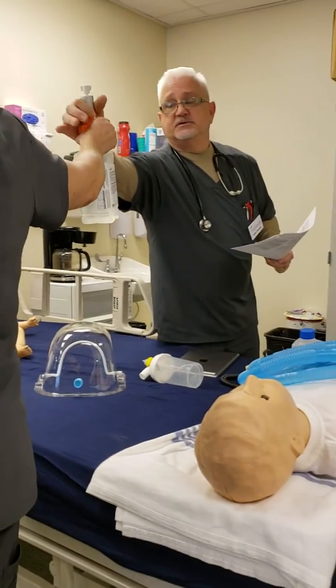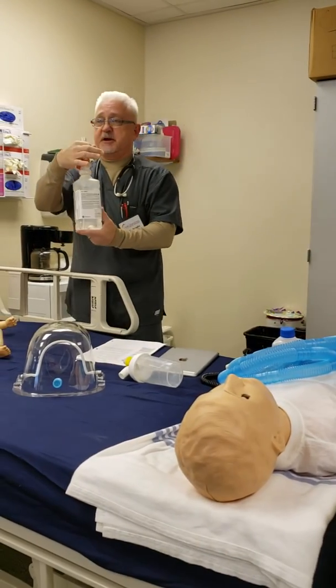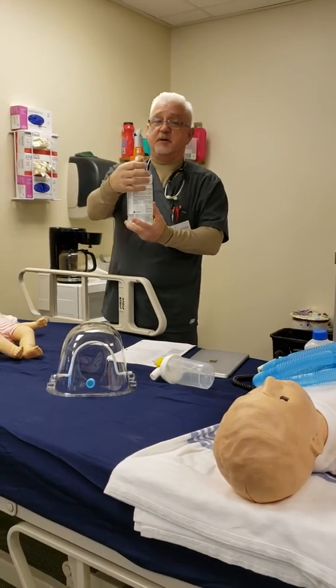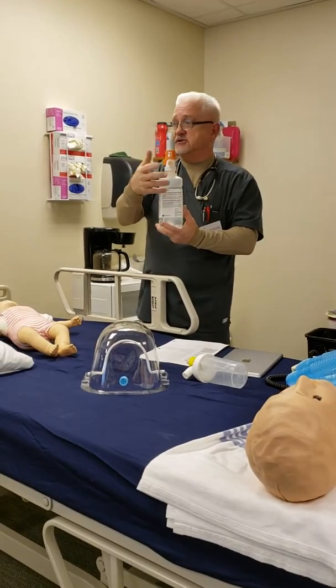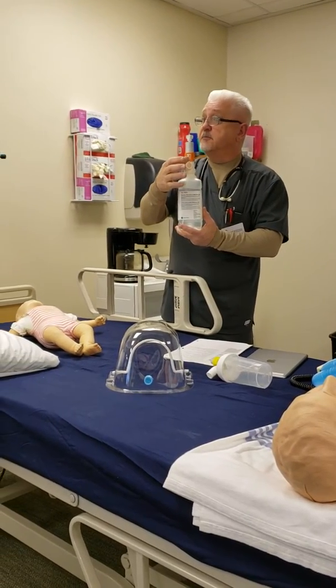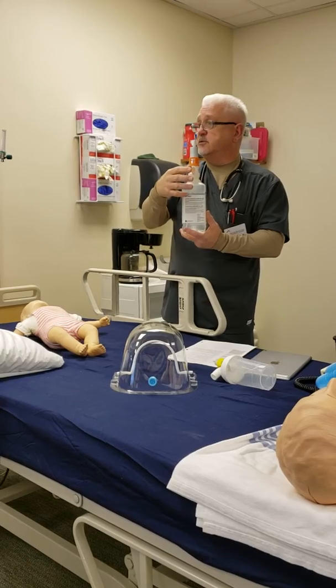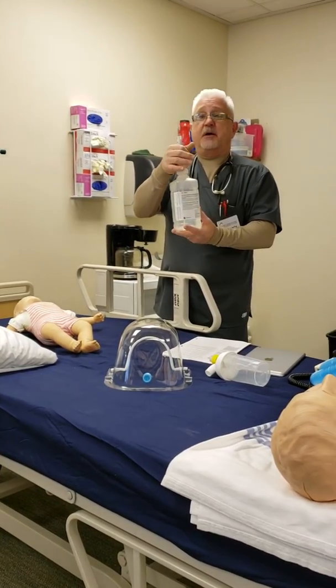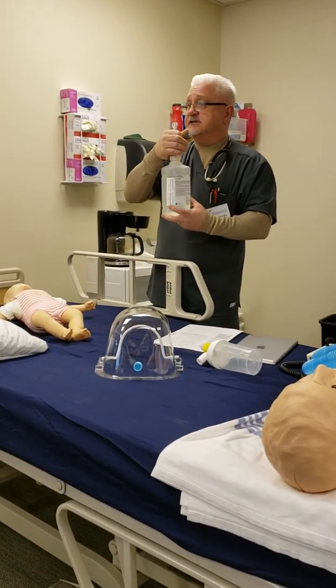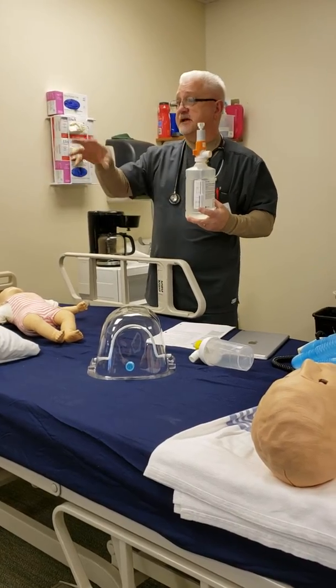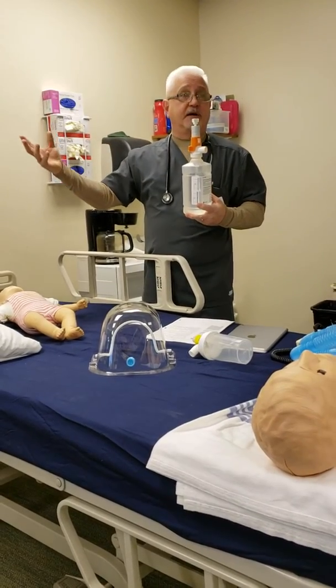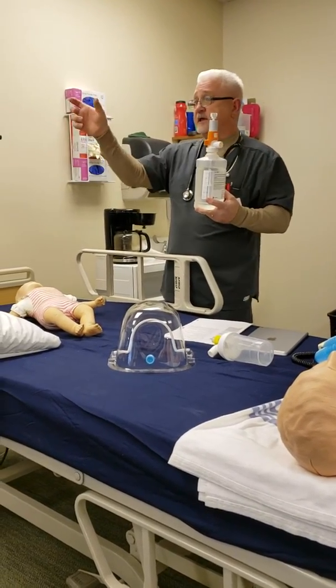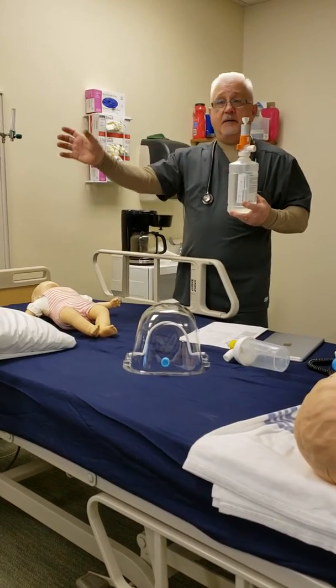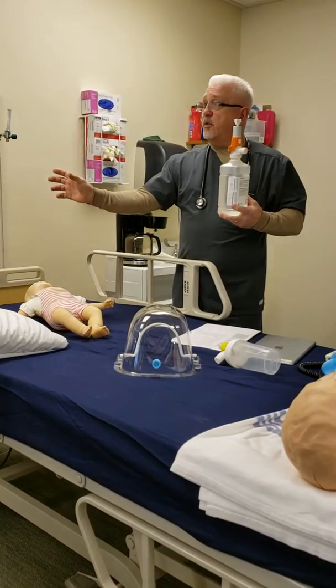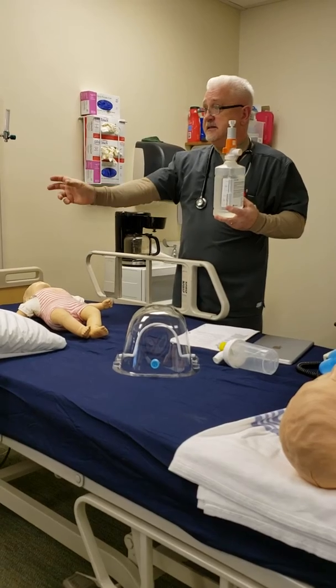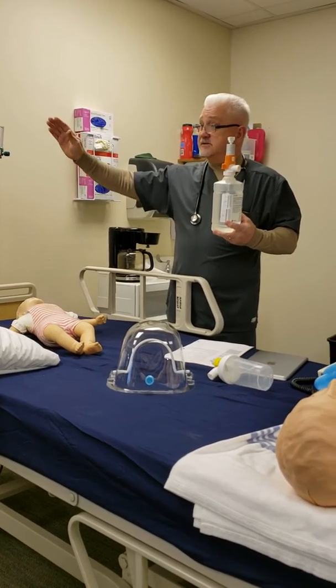So what we could use is something like this, and we would put a heated collar around the side, and we would measure the temperature of the gas to make sure that we were not providing the baby with too cool of a gas. But what I've seen in NICU is they use a heated wire circuit, very similar to what you see on mechanical ventilators, and they use the Fisher-Paykel little automatic water feed that fills up, and it does a blow-by.